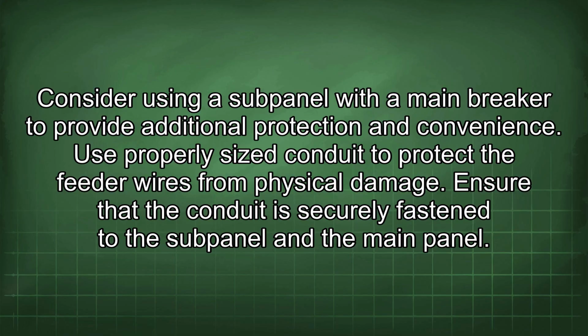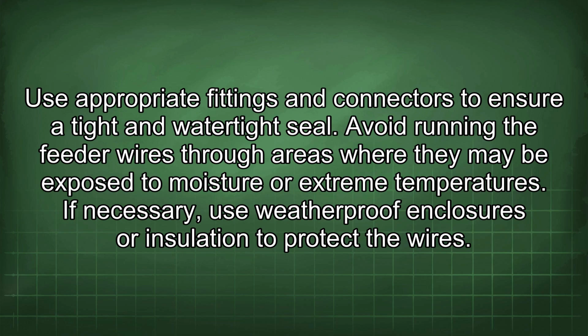Use properly sized conduit to protect the feeder wires from physical damage. Ensure that the conduit is securely fastened to the subpanel and the main panel. Use appropriate fittings and connectors to ensure a tight and watertight seal. Avoid running the feeder wires through areas where they may be exposed to moisture or extreme temperatures. If necessary, use weatherproof enclosures or insulation to protect the wires.